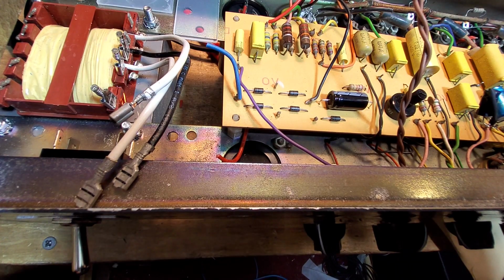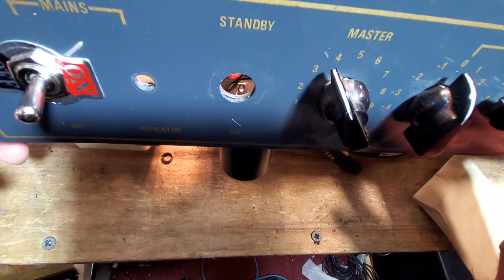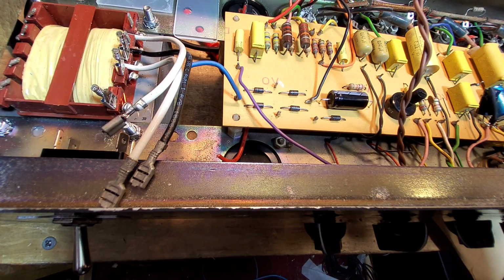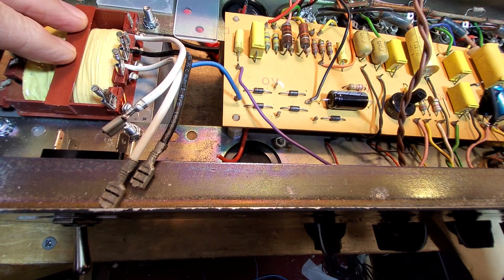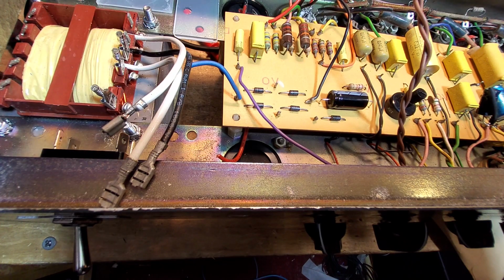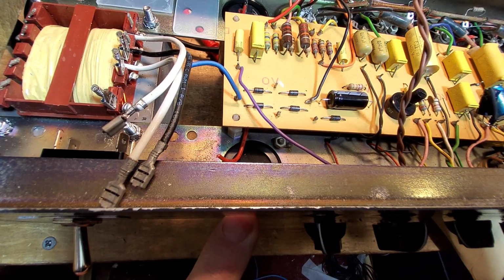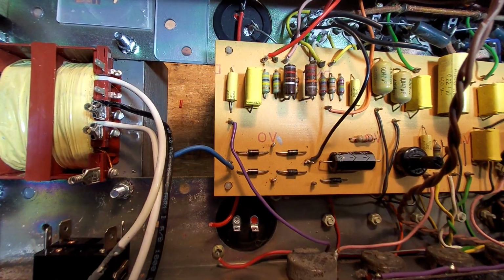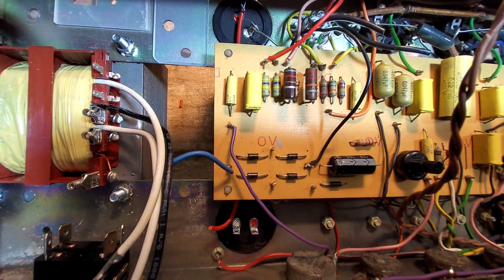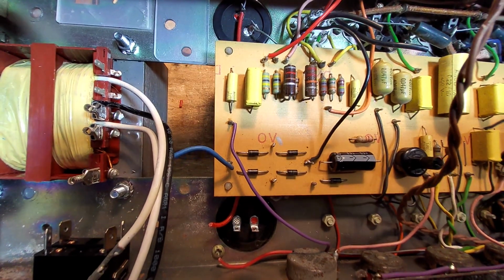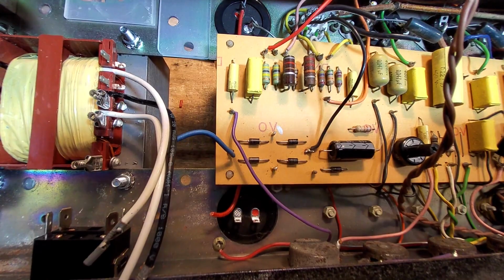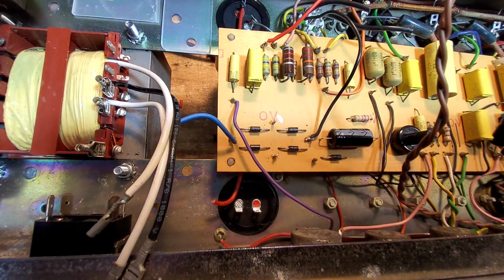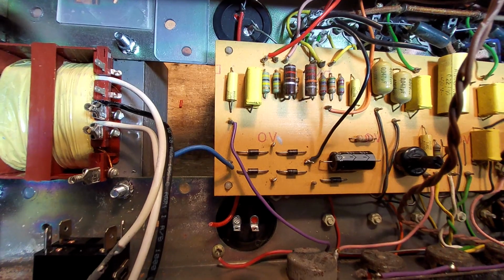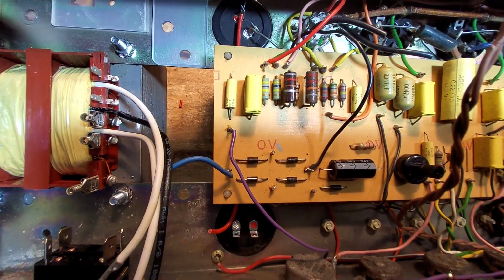I don't subscribe to standby switches for one thing. The capacitors are rated at 700 volts, so they're way over what this transformer kicks out, even before any power or current is drawn. The problem with having that standby switch right over that capacitor is that if it comes loose and somebody starts tightening it up and twists it, and it ends up contacting that capacitor, it could be really dangerous. I just think it's ludicrous to put a switch right above a capacitor like that.